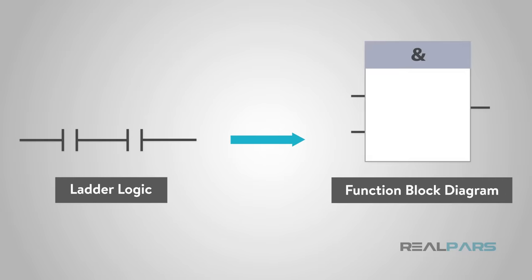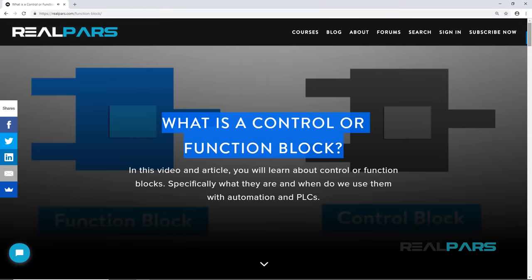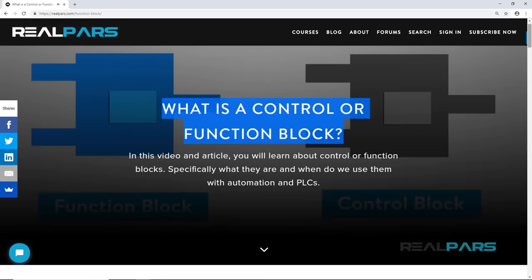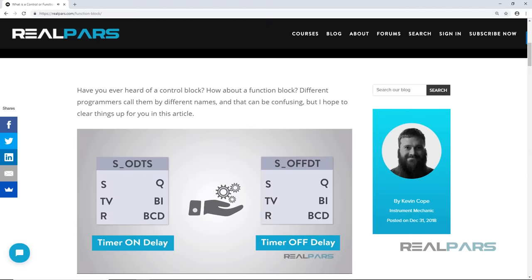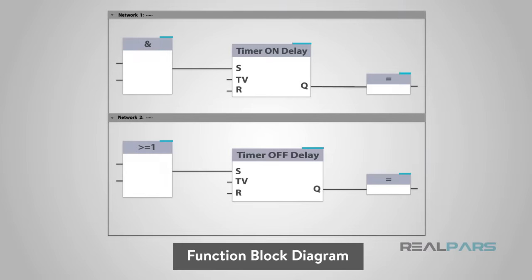Function block diagrams can essentially convert several lines of ladder logic into boxes. In the middle of the function block will be a symbol or text labeling the function block. This will describe the actual function of the block. There can be one or several inputs and an output for each function block. Those function blocks can be inputs to other function blocks as well.